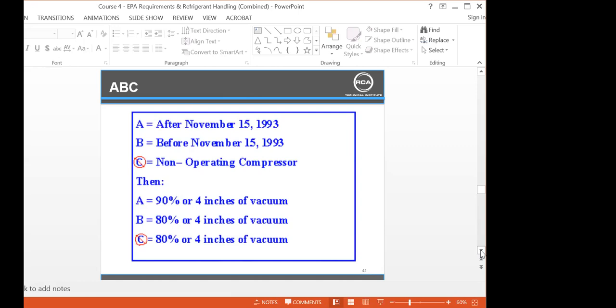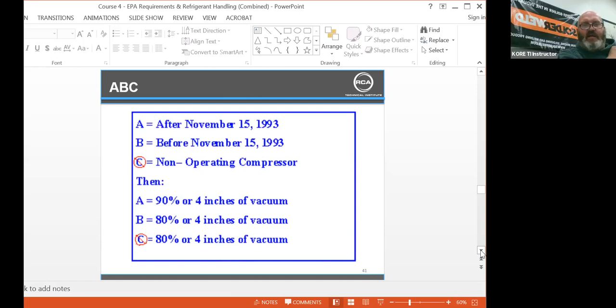ABCs. A is after November 15th, 1993. B, before November 1993. C equals non-operating compressor. Again, this is for you. A, after 1993, 4 inches of vacuum or 90%. B, 80% or 4 inches of vacuum. Or C, non-operating, 80% or 4 inches. Again, I've never even seen this, because our new equipment today definitely pulls that.